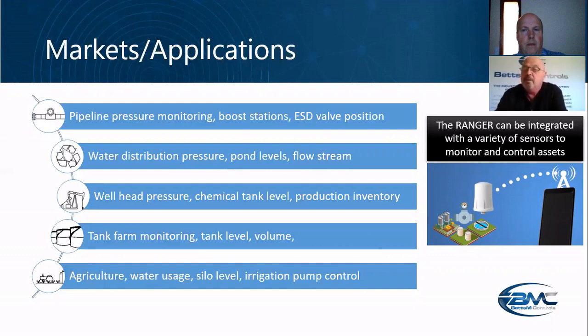The analog input they're using is actually the level of the water in the tunnel. And the temperature, they're actually taking the internal temperature from the Ranger. It's one of the internal variables, it tells you the temperature of the electronics. The electronics are probably a couple degrees warmer than ambient, so it gives you a good indication of whether it's hot or cold.